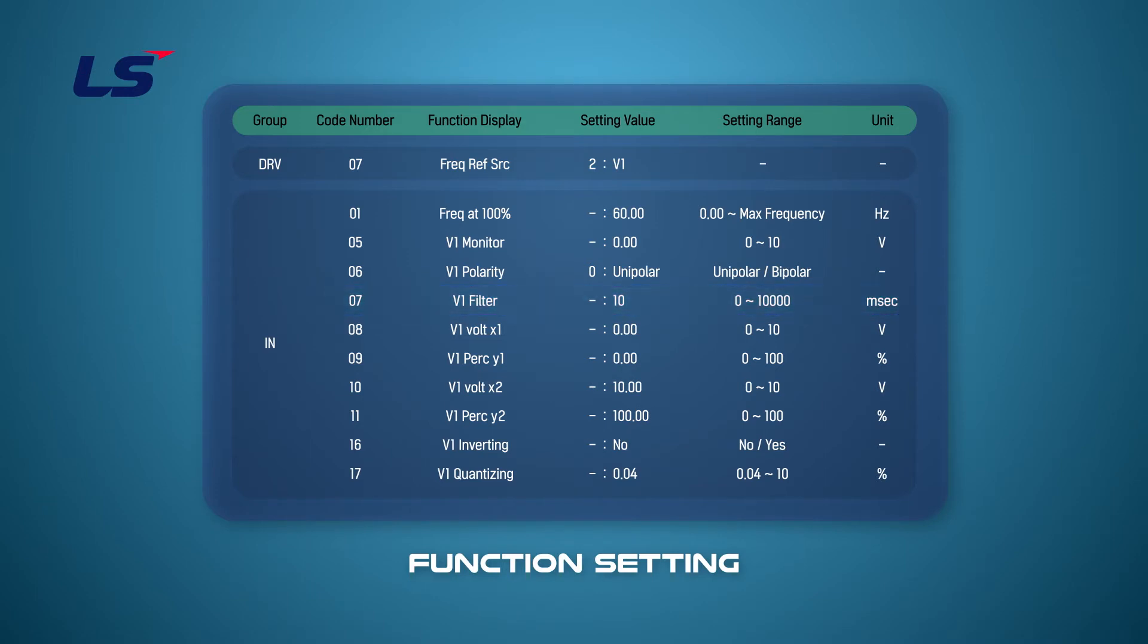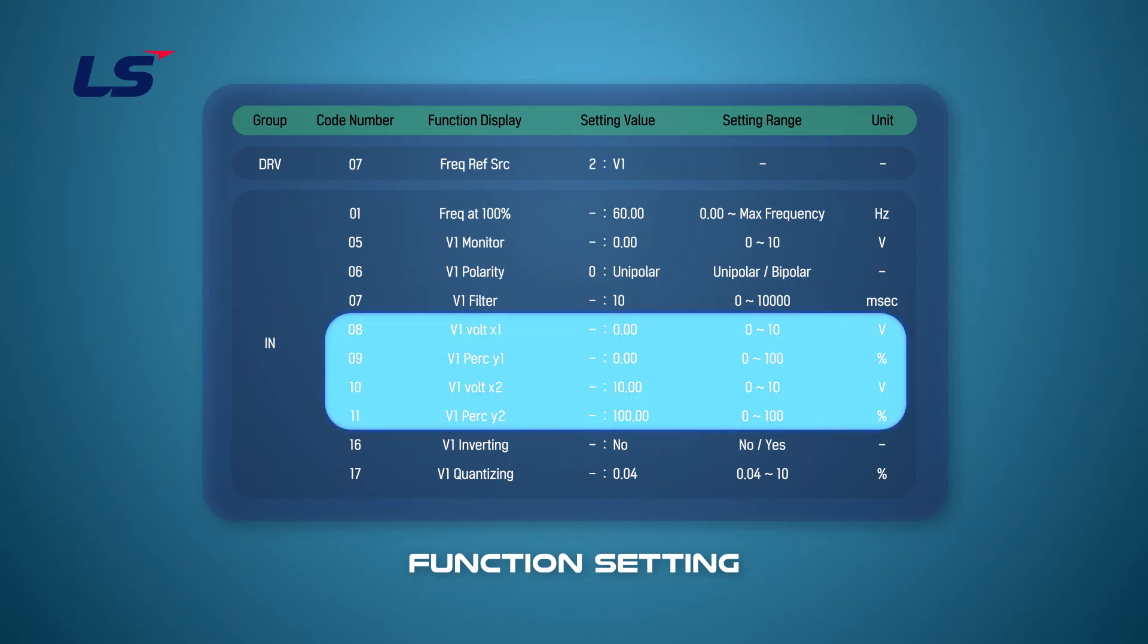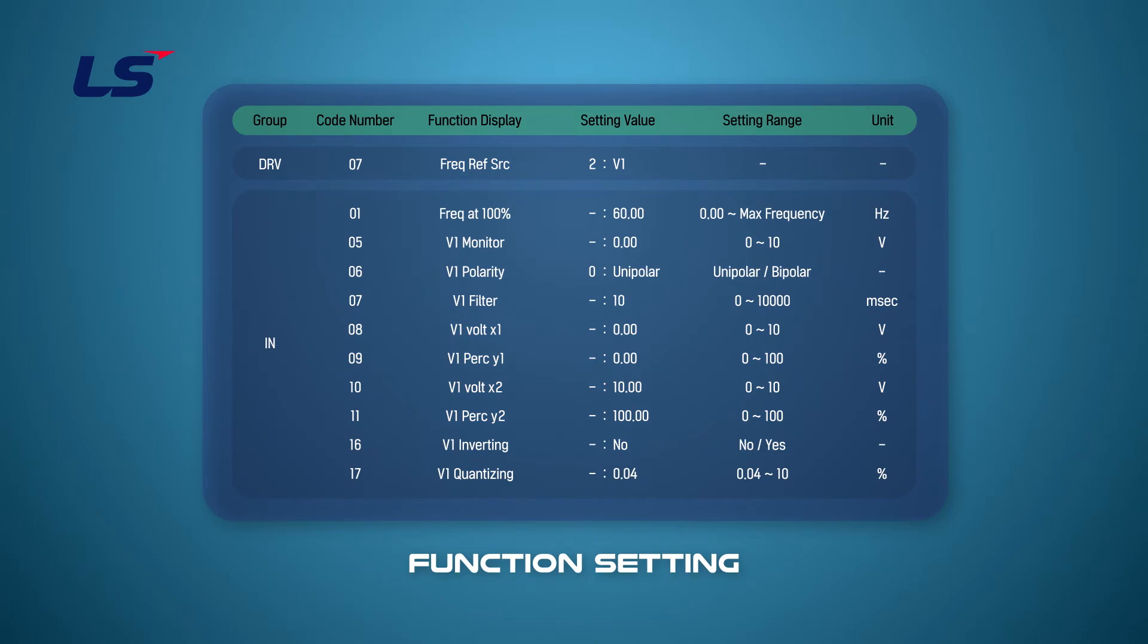You can set the time constant of filter for analog voltage inputs in IN-group 7. Parameters IN group 8 to 11 allow you to set the range of input voltage. You can set the minimum input voltage and the corresponding frequency, and maximum input voltage and corresponding frequency. The frequency corresponding to 100% of the analog input can be set in parameter IN group 1.